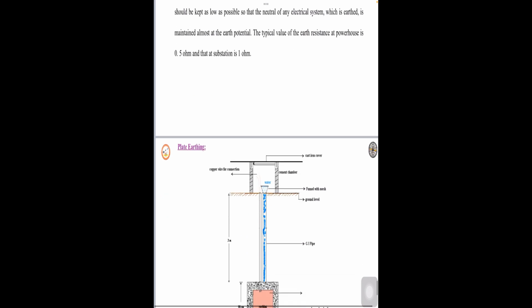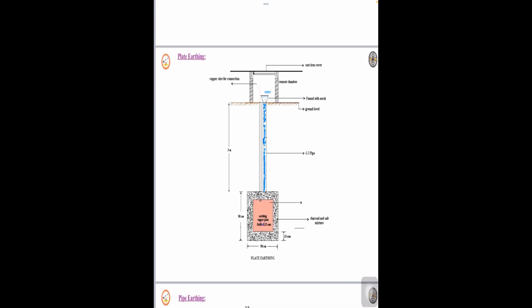When we observe the diagram of plate earthing, you can see it has copper wire for connection, cement chambers, a cast iron cover, a funnel with mesh to let the water flow, and the ground level. From the ground level there is a GI pipe about 3 meters long, and below 3 meters there is an earthing plate of 90 by 90 centimeters, surrounded by a charcoal and salt mixture.